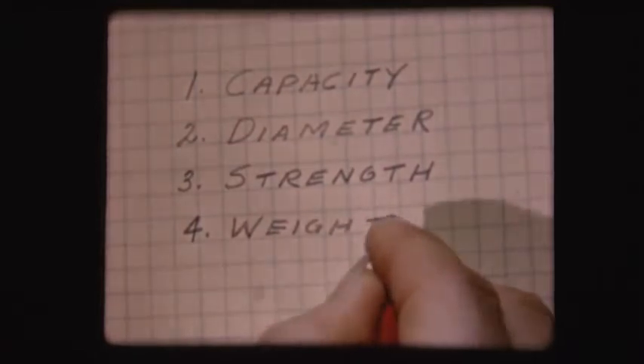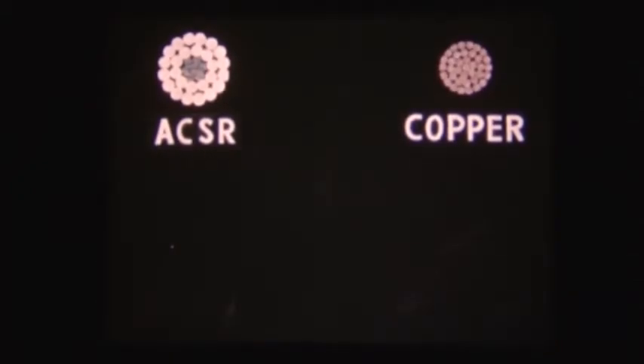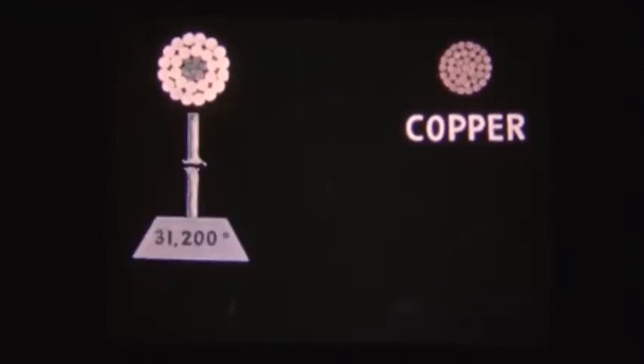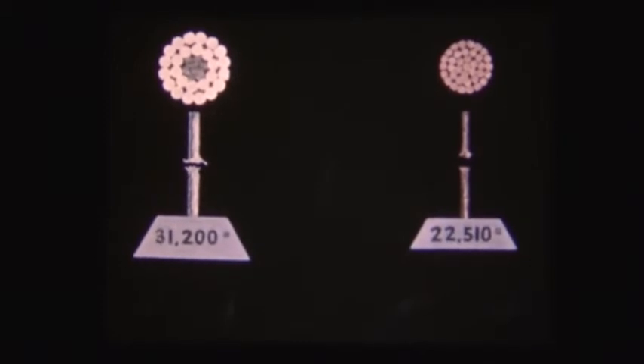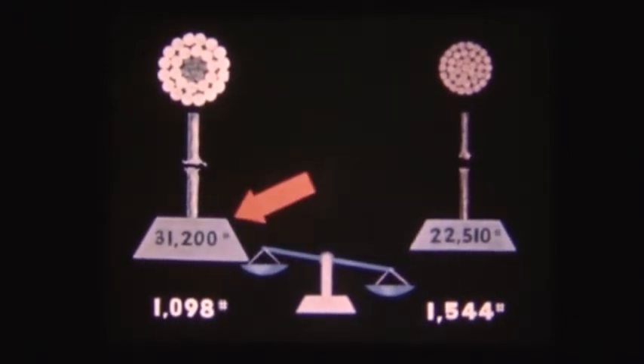An important one is the ratio between strength and weight. Let's go back to our examples of ACSR and copper of equal carrying capacity. We find that the ACSR has a breaking strength of 31,200 pounds, as compared with 22,510 pounds for the non-reinforced copper. The weight of a thousand feet of ACSR in this particular size and design is 1,098 pounds, compared with 1,544 pounds for the same length of the equivalent copper. In other words, the ACSR in this particular case is both stronger and lighter than the smaller diametered copper of the same carrying capacity.